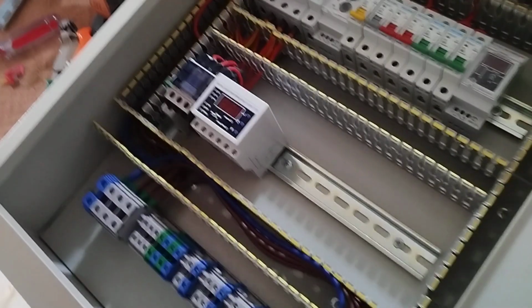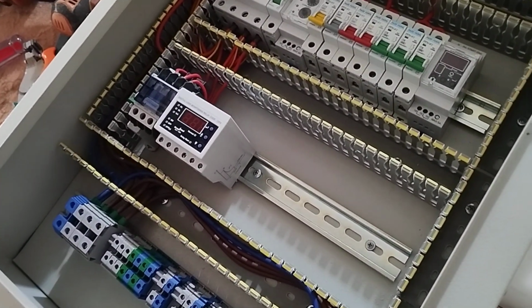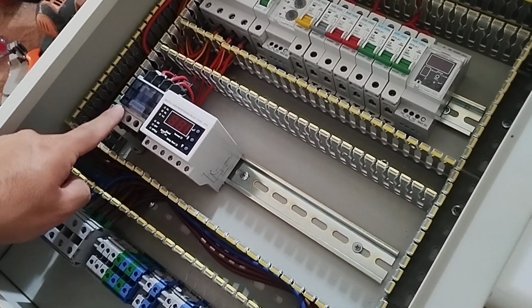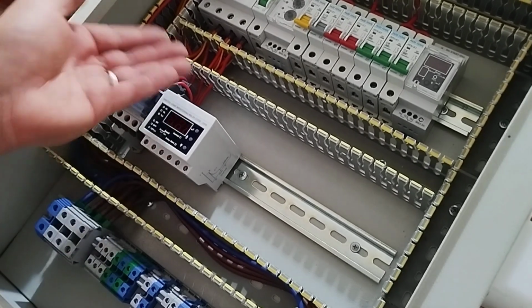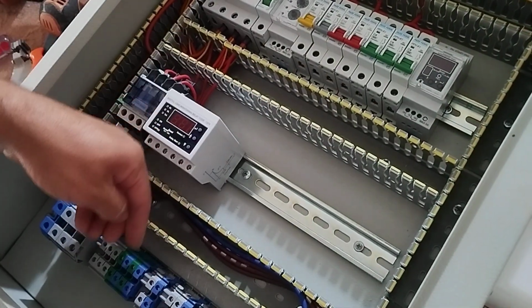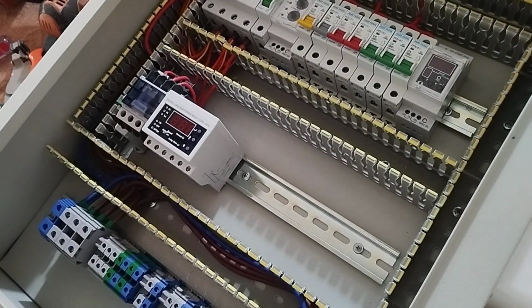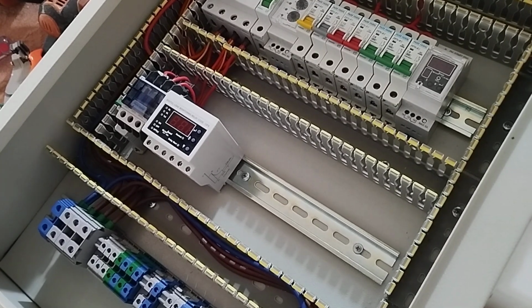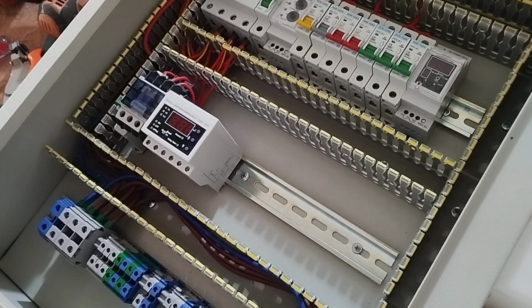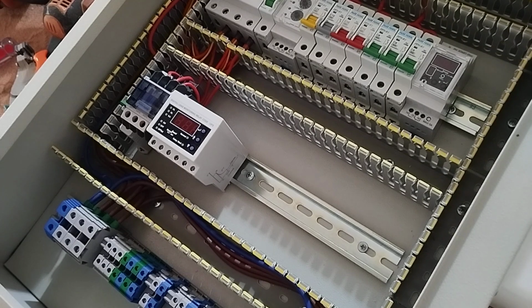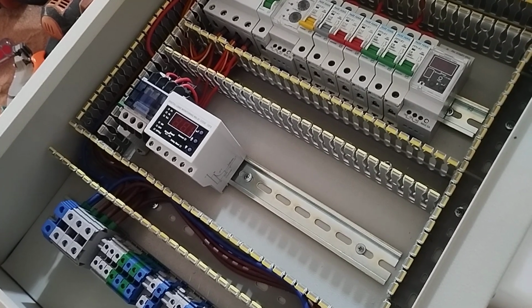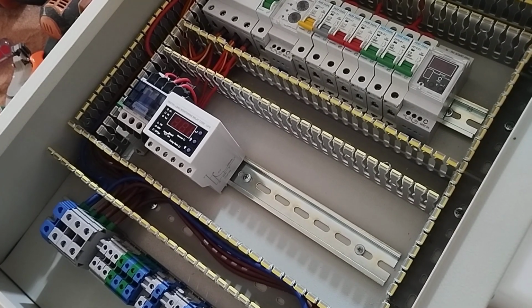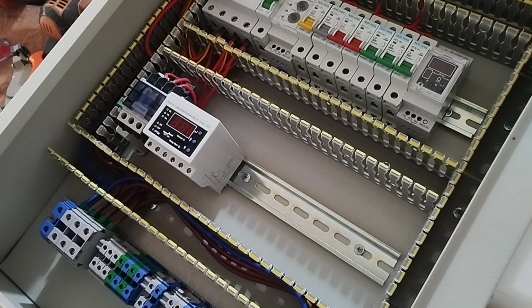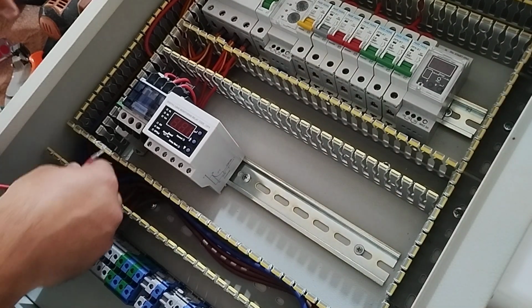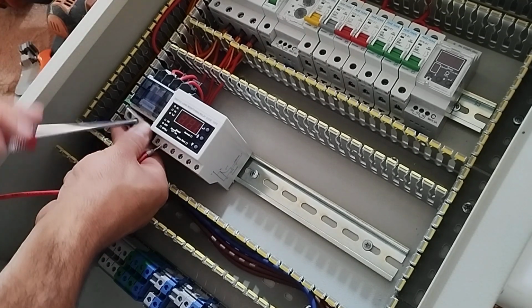In this step, we connect three phases from the output of the contactor to the three-phase output terminals. But before that, we pass the three phases through the hole of the current controller relay to measure and display the current flowing through the consumer, so that in the event of an error, the circuit is interrupted by the contactor. This is for the first phase.